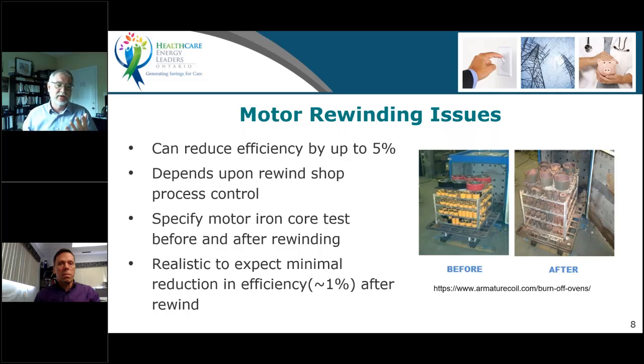So make sure that if you're getting motors rewound, you get a core test before and after to demonstrate that the core hasn't changed, and put some limits on it. If it comes back too low, then you basically don't want that. You're not going to pay for that rewind.